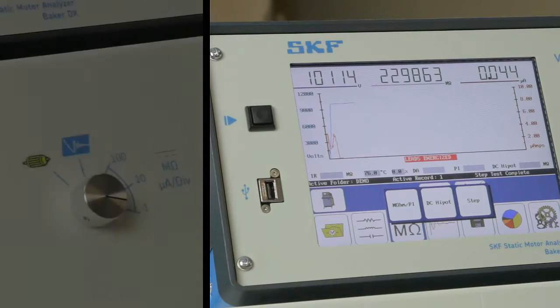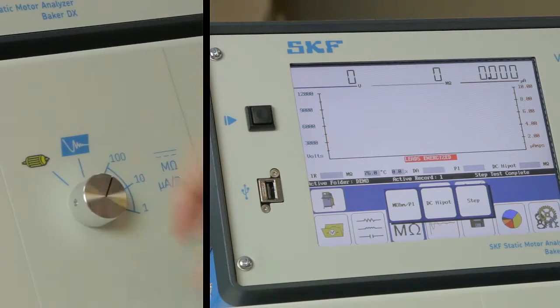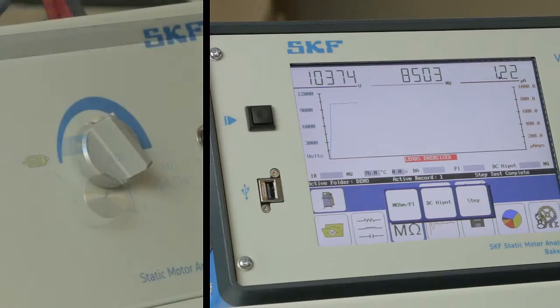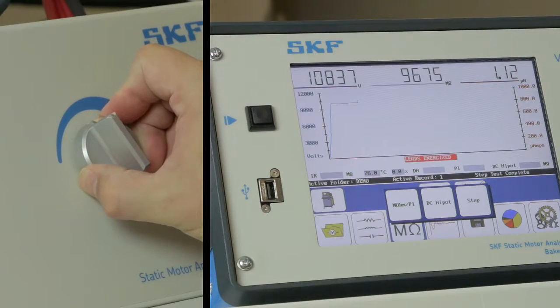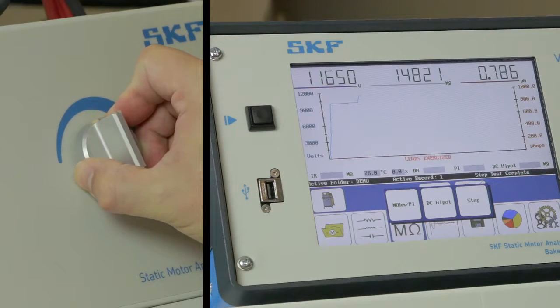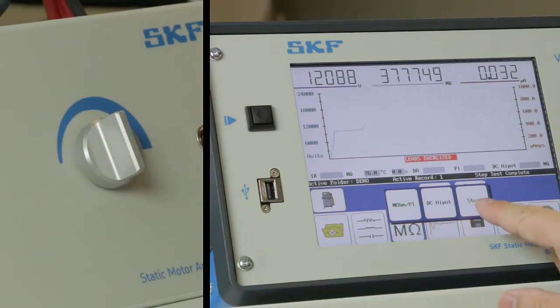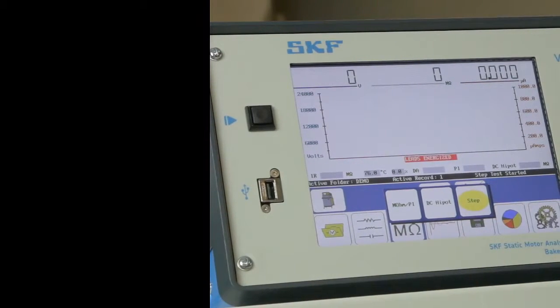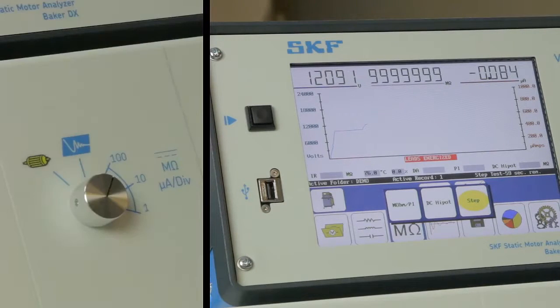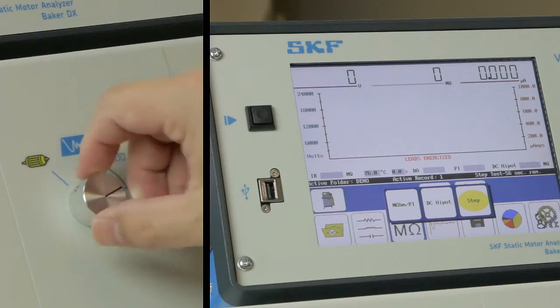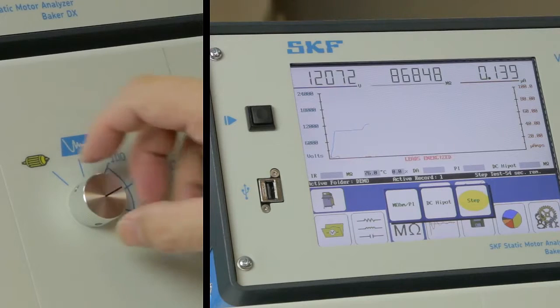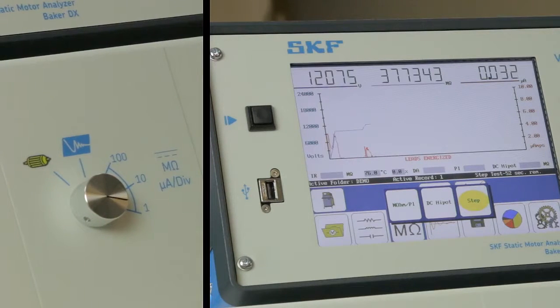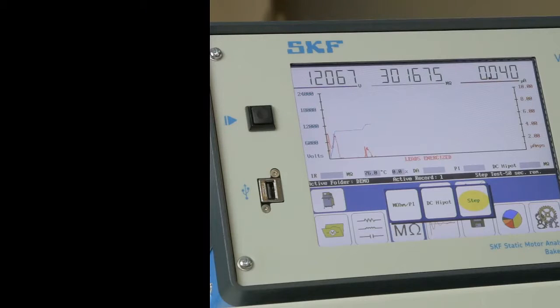When the step timer is complete, return the power pack's function knob to 100 microamps per division. This will avoid an overcurrent trip when you increase the voltage. Turn the voltage control knob smoothly to increase the voltage to the next desired level, and press step. Again, adjust the current scale with the function knob as before. Continue this procedure for all steps.